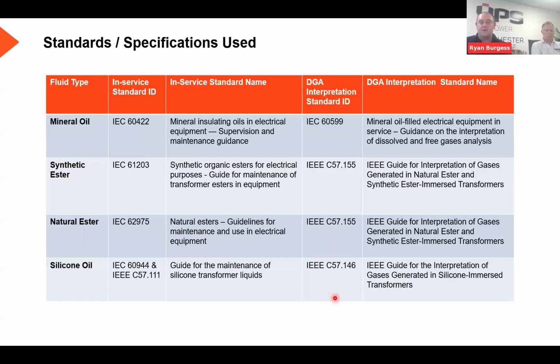When it comes to the DGA standards, they're not actually standards, they are guidelines. By that, we mean they don't have hard and fast limits, due to the way the data is collected by the IEC. They give you a range, and it also allows for certain types of assets operating differently. So you can't have the same specification just by saying a transformer. You can't just say this one limit for every transformer.